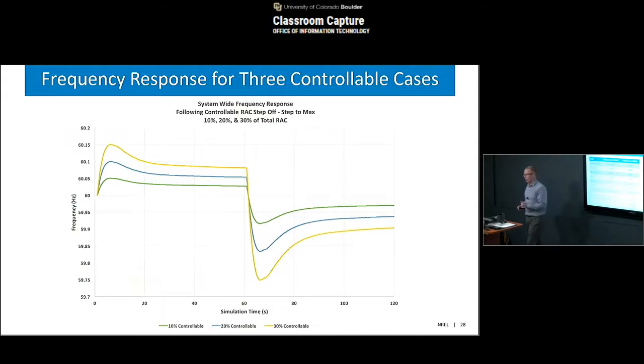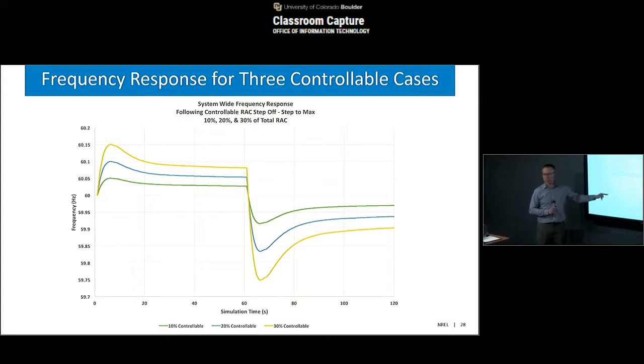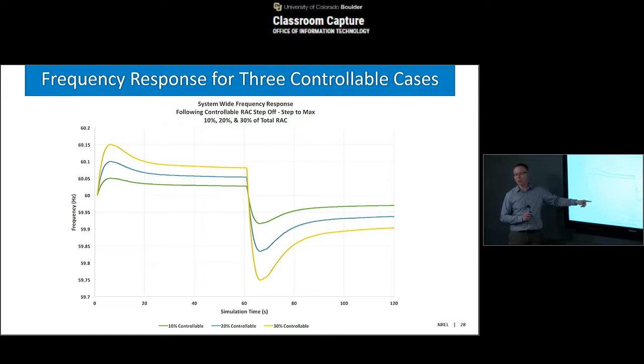Here are the three different cases: 10%, 20%, and 30%. A couple things about power system frequency: we run at 60 hertz here in the US, not 50 hertz like in Europe and some other places. Your dead band for control goes from 60 to 60.2 hertz. Above that is an over-frequency event, and you start shedding load to protect equipment at 60.2. At 59.8, you also start shedding load. There are other remedial actions in between, but hitting 59.8 is really, really bad. People get fired for this.